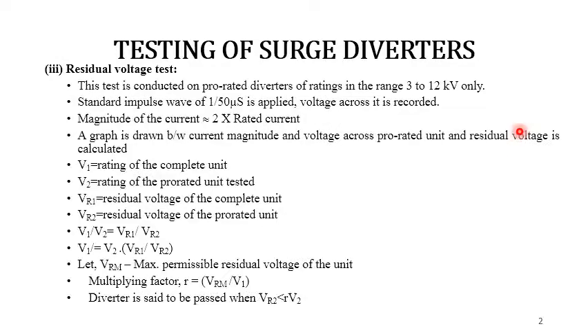Then we have the residual voltage test. This is conducted on prorated diverters of rating in the range from 3 to 12 kV only. The voltage developed across the non-linear resistor, that is NLR, during the flow of surge current through the arrester is called residual voltage. The standard impulse waveform of 1/50 microsecond is applied and it is recorded, and this can be recorded by using the CRO.